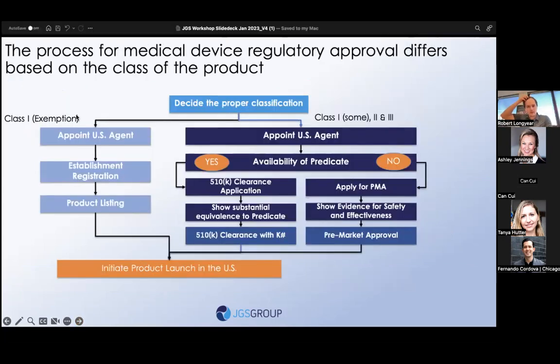This is the publicly available pathway map for medical devices. So we look for the proper classification - there's publicly listed products that fall under various different classifications for the intended use. Then we go through and look at these various processes. Class one is exempt from filings, so you're just registering with the FDA, putting your company name and information on the website so they can contact you if they decide your device is potentially dangerous, not efficacious, or should really be classified as a class two or class three. Then for class two, class three, and some class ones, you're really going to go through a process of trying to identify a predicate device in terms of the technology.